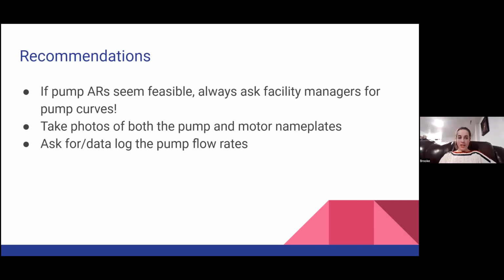So some of the recommendations would be, if any of these pump ARs seem possible, always ask if there are pump curves available, so that you can make sure you get them. And really important to make sure you take a picture of the pump and the motor nameplate, not just the motor nameplate, but also the pump nameplate. And then it's good to ask for or log the pump flow rates and power as well.